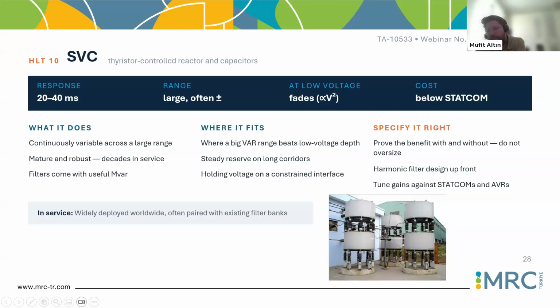style or the new technology, you can also use this one, because the connection point requirements are not so fast. You can use this one. As I said, between the STATCOM, the differences are mainly the speed. Of course, there is voltage dependency on this SVC since you are controlling the impedance. SVCs are cheap, of course, by comparison. But the installation, the flexibility and compactness are better in the STATCOM if you compare SVCs and STATCOMs. Again, you need to model the things in your system.